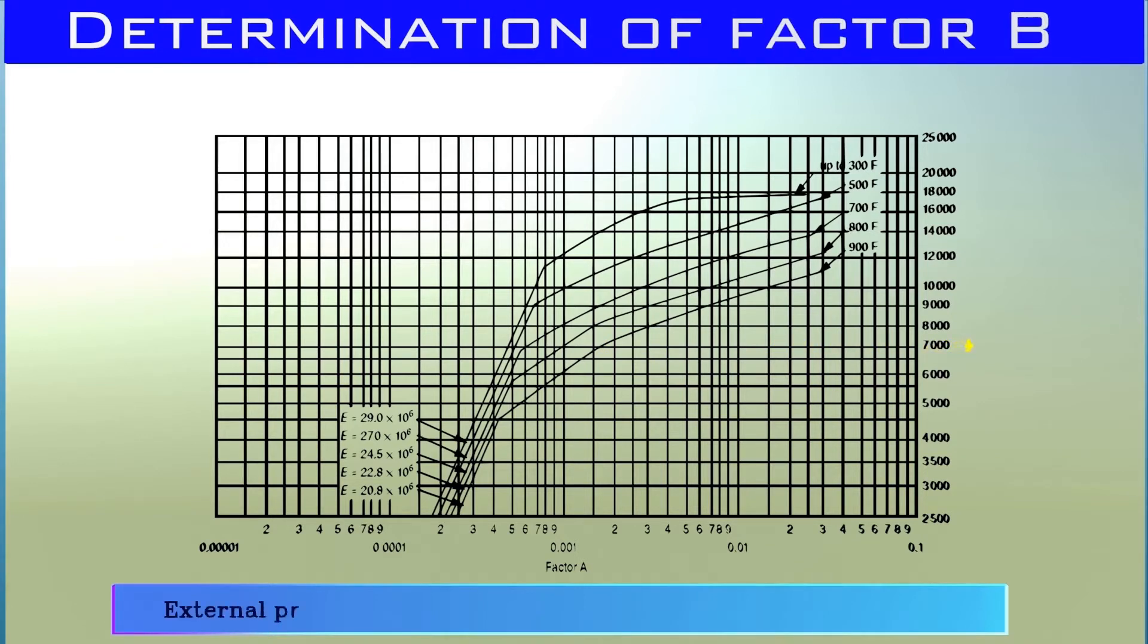Here is the external pressure chart for factor B, only applicable to carbon and low-alloy steels. The horizontal axis is for factor A and the vertical axis for factor B values. These curves represent the operating temperature and relative strength of the materials of construction of the vessel.